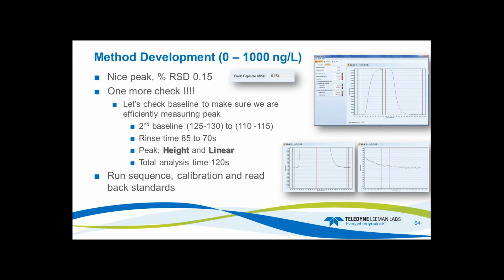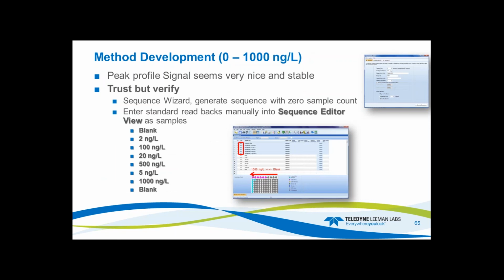And then I'm going to read back some standards. The peak profile seems very nice and stable. Trust but verify. So in the sequence wizard, I'm going to generate the sequence, the calibration without a sample count. In this case, I had my high standard to the left and my blank to the right. So it came over and then it worked this way. You can do it however you want. You can put your standards out in these racks, in the bottom racks, you can put them over here. You can do almost anything you want with this system.